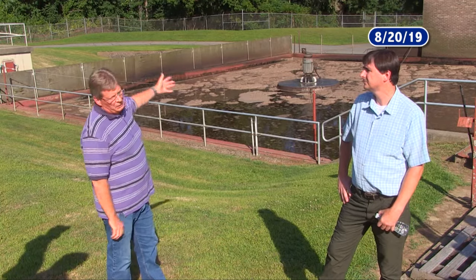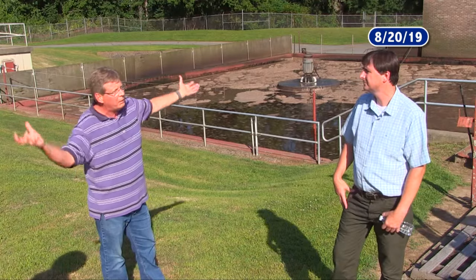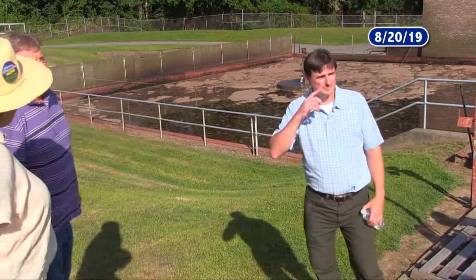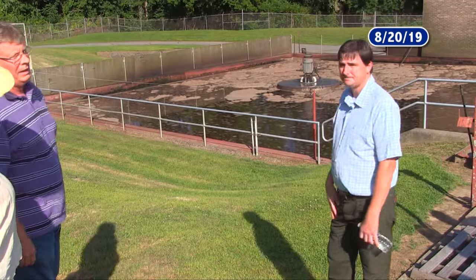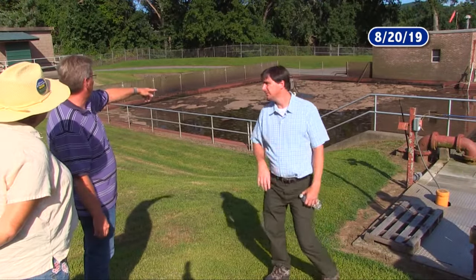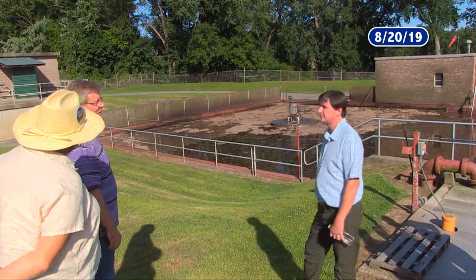And we have to call a crane once a month to lift this out, set it off to the side so we can clean all the rags off. This thing in the middle? Yep. And put it back in again. Crane every month. Put it on the lawn? No, it puts it right over there on the table. And we spend 3 hours cleaning it off once a month and putting it back in again. And then it starts. We just cleaned it last Friday. You can already see rag material starting to gather on it.